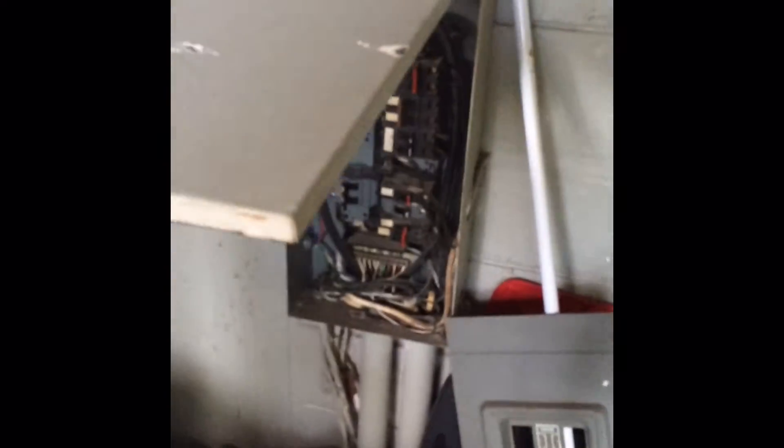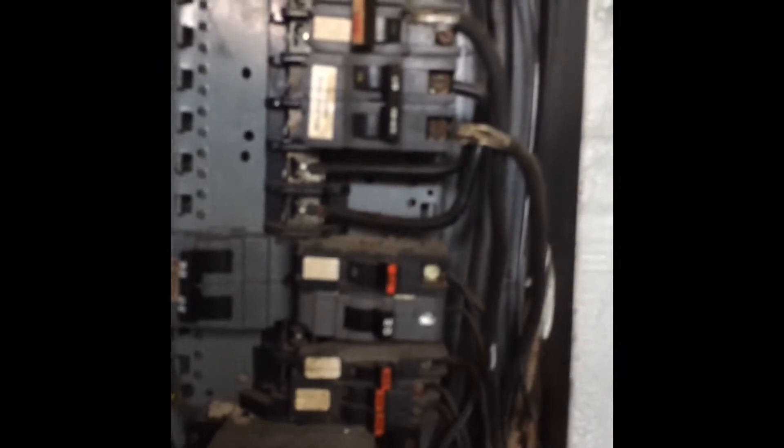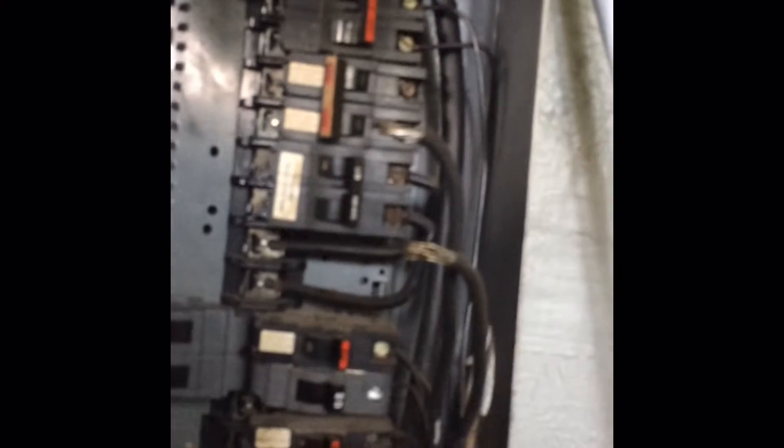Today we're talking about replacing breakers in an old panel box. This is the Federal Pacific panel box, and you see that I've already taken these two wires off. Something important to know is that when you're dealing with aluminum wires, you need to always insulate them or use an antioxidant — something that's going to help the aluminum wires not get corroded.